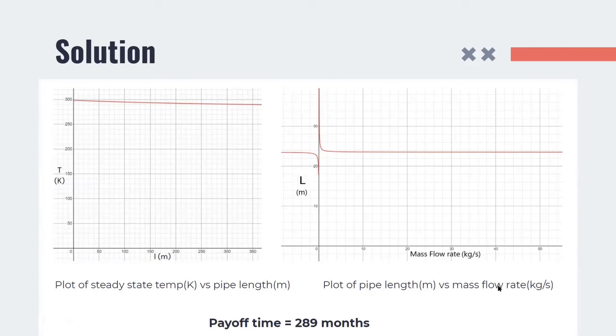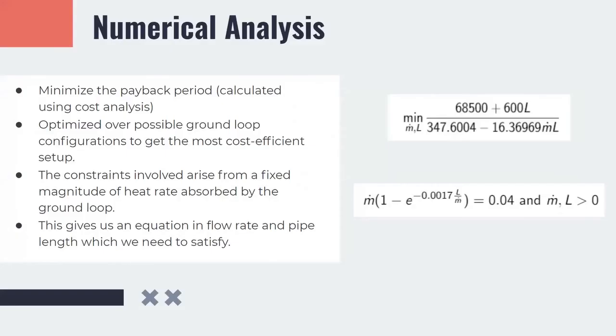Using these for the constraint optimization, we get that the payoff time is 289 months. The numerical analysis is done as follows. We use the cost analysis to get a rough expression for the payback period in months, which is then optimized over possible ground loop configurations to get the most cost efficient setup. The constraints involved arise from a fixed magnitude of heat rate absorbed by the ground loop. This gives us an equation in flow rate and pipe length, which we need to satisfy.